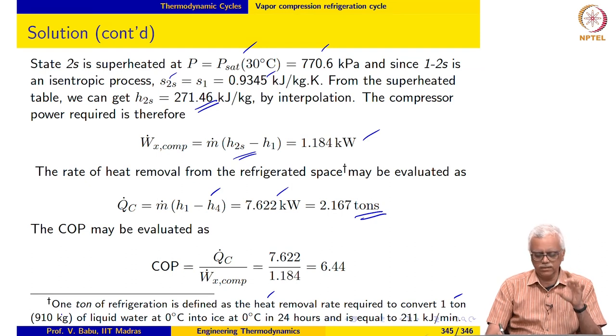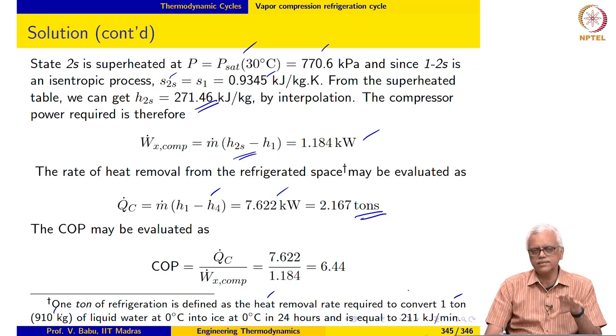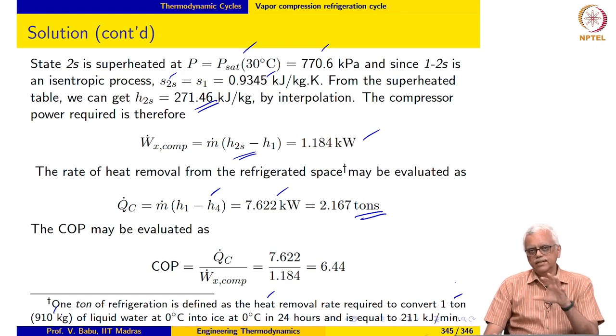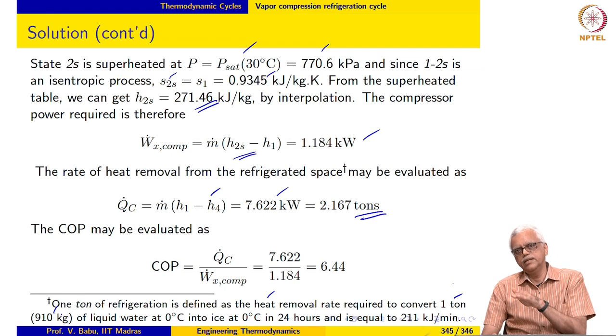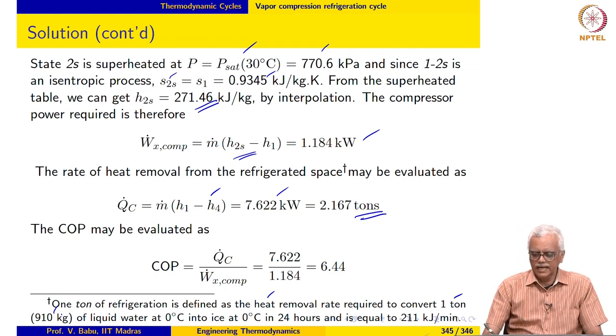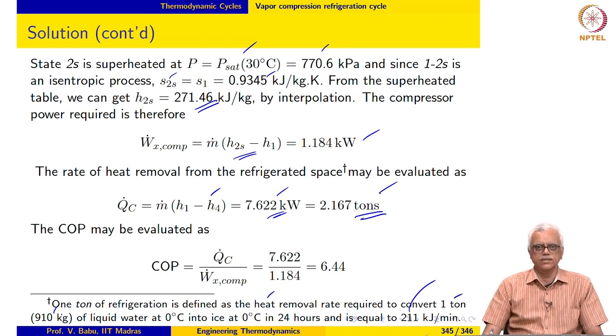1 ton here is 910 kilogram. It is not 1 metric ton, it is 1 ton which is equal to 910 kilograms of liquid water at 0 degree Celsius into ice at 0 degree Celsius in a span of 24 hours. It is the rate at which heat must be removed from 1 ton of water at 0 degree Celsius to convert it into ice at 0 degree Celsius in a span of 24 hours and is equal to 211 kilojoule per minute. If I convert this to tons, I get this to be 2.167 tons of refrigeration effect.